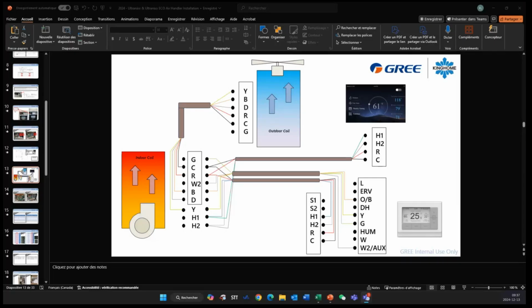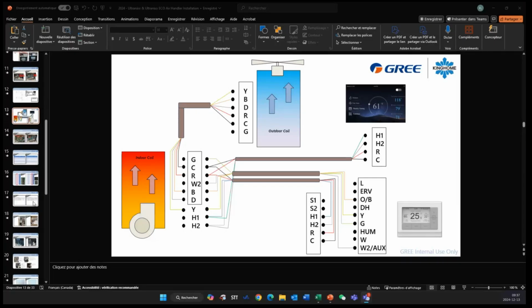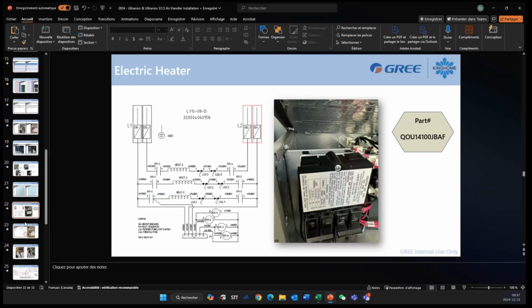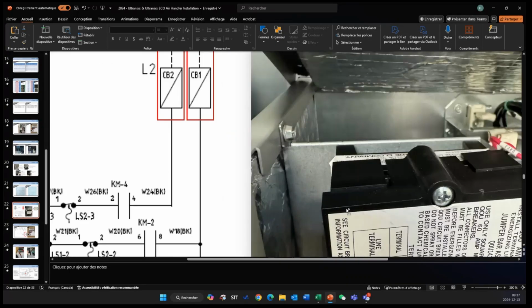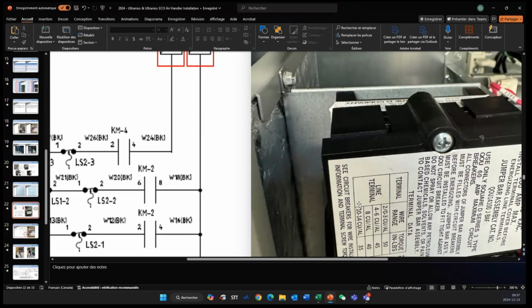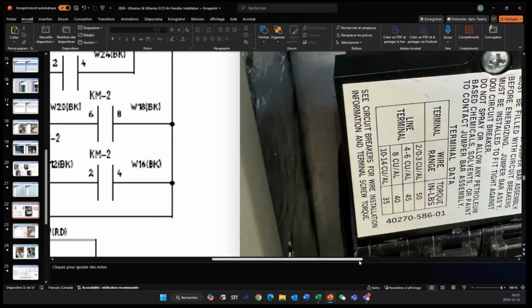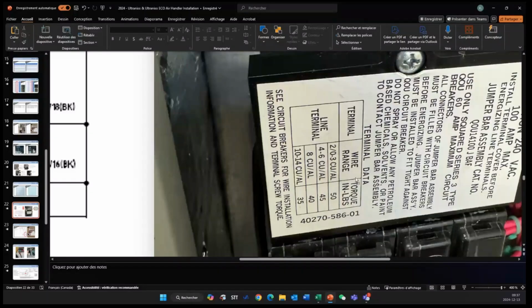Sorry. So the single point attachment, a lot of times we have an electric air handler with 100 amps coming down. Are there specs on it, on what size wire it can take? Yes, it's good for 100 amp. This connector here, I think you have it right here. Oh, perfect. You have a range here for your wire if you use aluminum or copper wires, and also the torque you need to apply when you torque those wires.